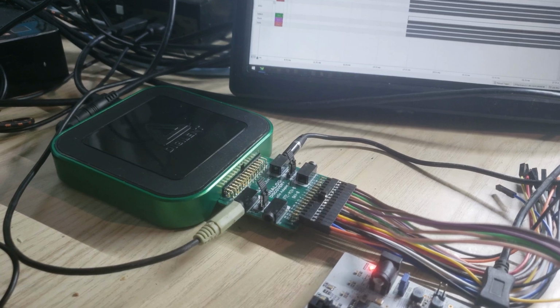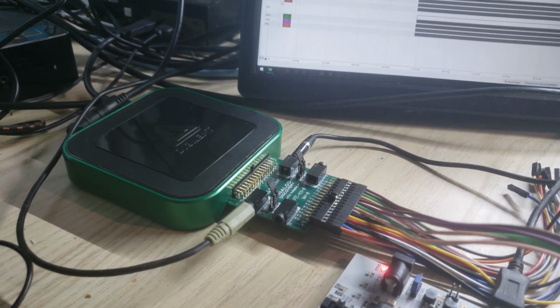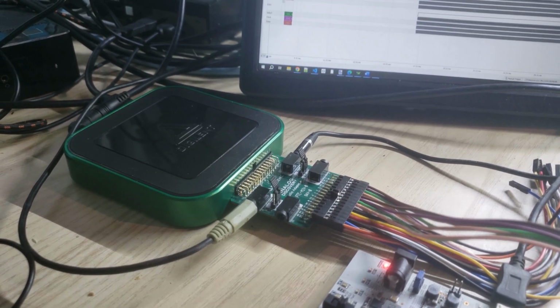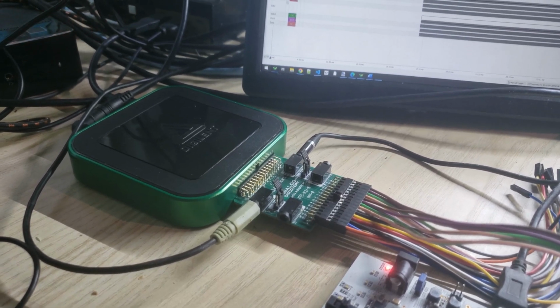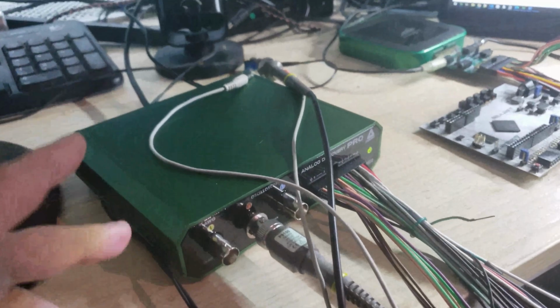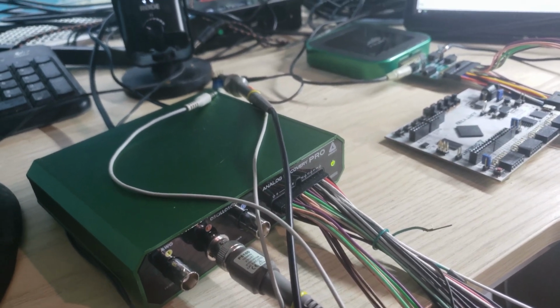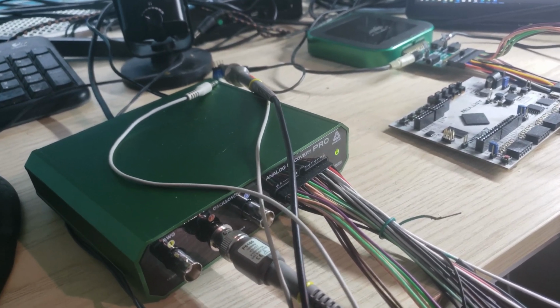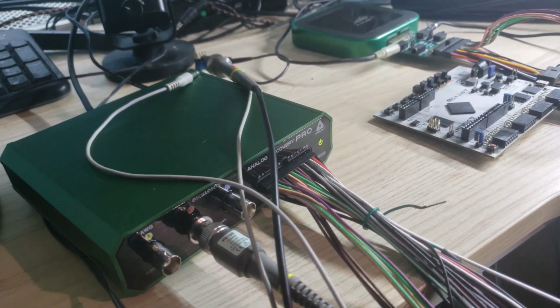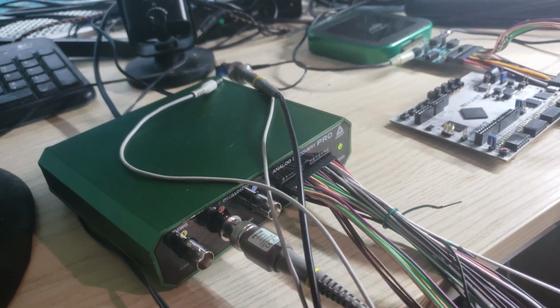We have a BNC adapter for the AD3 that lets you break out to BNC scope probes and use those. But it's a separate piece of equipment that you buy separately and then have to plug into the device. So when we went over to the Pro, we understood that bandwidth is really critical for professionals, and being able to capture as high speed of a signal as you can is super critical. So in this case, we just built the BNC connectors directly into the device itself.